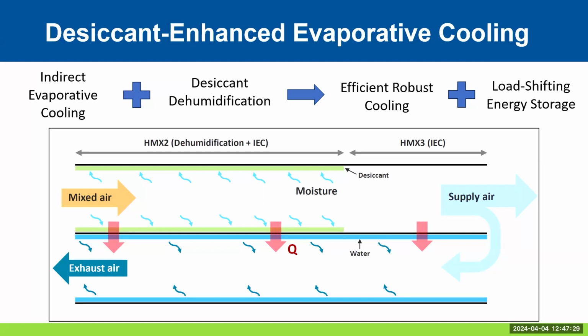I'll jump in: typical air conditioning equipment can't independently control humidity and temperature. If you want it to dehumidify, you have to cool the air down a lot. So if you want to dry out a space, you might end up overcooling it, or in many situations, while cooling a space you end up doing more dehumidification than necessary, wasting energy in the process.